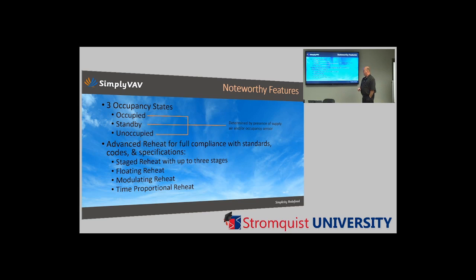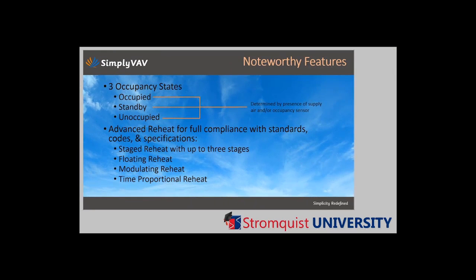From the occupancy side, there's really 3 occupancy states if you're dealing with, per se, a conference room or someplace that doesn't have a regular occupancy schedule to it. It can be determined by any number of things, by airflow or by an actual occupancy sensor on the front of the device. And it'll essentially give you 3 modes: occupied, standby, or unoccupied.